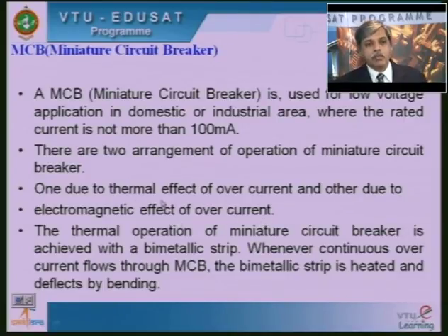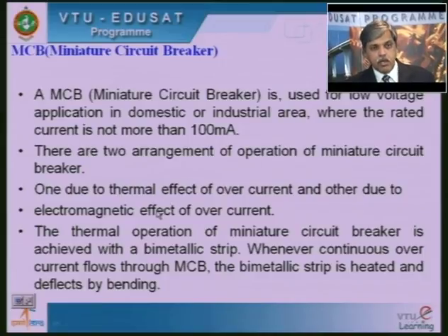So one will work on the thermal effect, that is whenever the circuit draws an overcurrent, that is current larger than the rated value, there will be a thermal effect, so that makes the circuit breaker disconnect the circuit from the supply. And then there will be the electromagnetic effect, the current that is drawn will produce magnetism, so that will cause the circuit breaker to operate when there is an excessive current drawn by the system. Both operations are for protecting the system. But the difference between the fuse and the MCB is that the fuse melts. So whenever the fuse melts, I need to do a replacement, otherwise the continuity of supply will not be there. But the MCB is not like that. When it trips, after normalcy, I can just close it back.